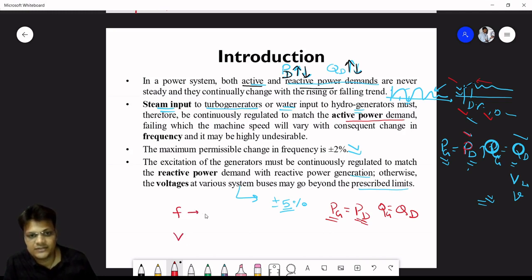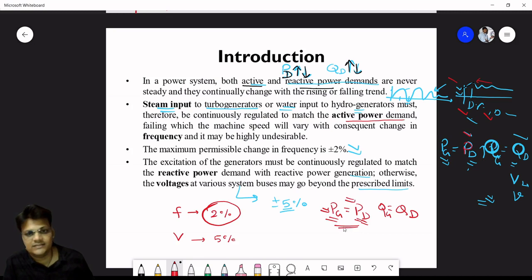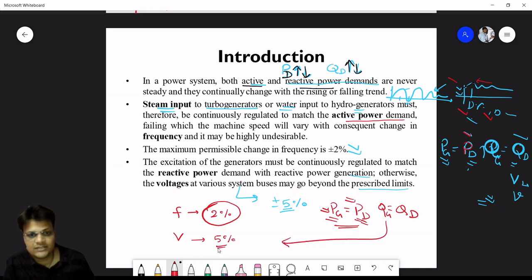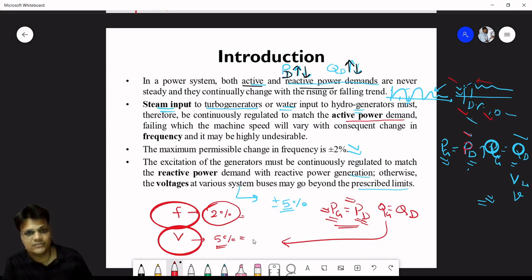The permissible limit of frequency deviation is ±2% and voltage is ±5%. If we maintain frequency within 2%, we can manage active power generation equal to demand. For reactive power, we manage voltage up to 5%. Load frequency control is covered in Unit 3, and excitation voltage control in Unit 4.